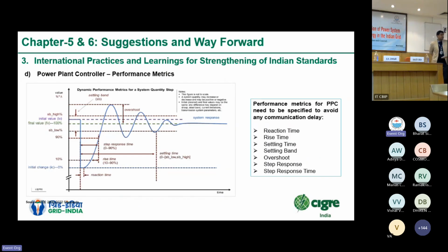Again, for the power plant controllers, several interactions were discussed in this slide as well as in the report. Different timings and different parameters have caused oscillations and small signal stability issues. There are different sets of parameters and their communication delays. They all need to be tuned so that the plant is able to provide steady state voltage control as desired in the CEA standards. So all these parameters and performance metrics need to be defined and elaborated in the standard.